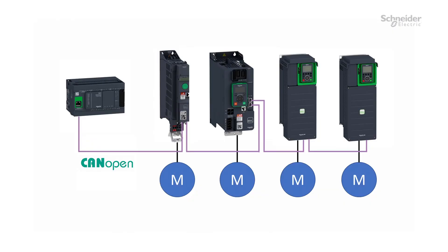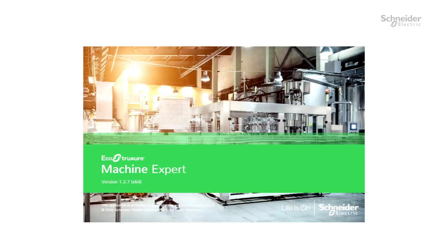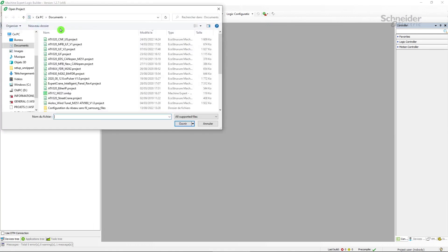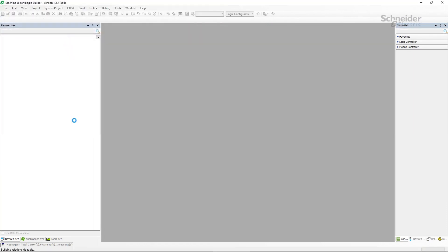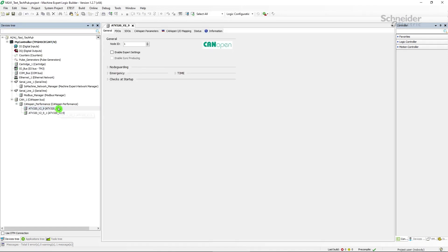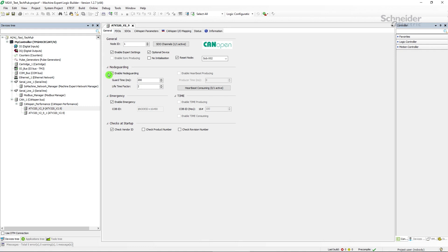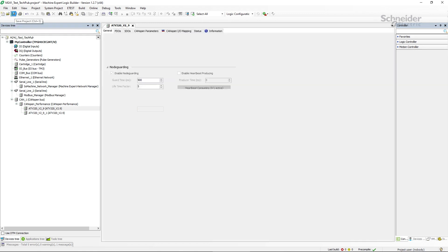For other protocols such as PROFINET, PROFIBUS, and CANOPEN, the timeout is set by the PLC. Let's take the example of CANOPEN with the Machine Expert software. Open your project and click on your drive in the CANOPEN Performance tab. In the General section, check Enable Expert Settings. On the Node Guarding drop-down menu, increase the Guard Time and the Lifetime factor. Always verify that the new setting is suitable for your application and cannot result in hazard due to delayed time detection. Save your project and download the new program to the PLC.